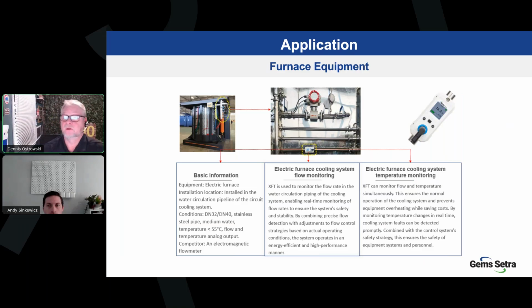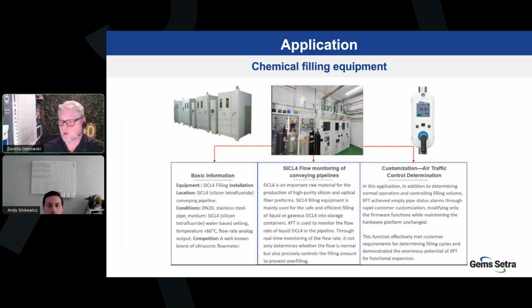Okay, and we have another application for chemicals. We had mentioned before, chemicals can be quite caustic. A lot of corrosion can happen in your equipment and in devices that are in line, right? So if you've got a clamp on, you eliminate those risks. You're not going to have any kind of contamination. You're not going to have any kind of corrosion. So it doesn't matter, as long as you know that sound velocity, right? As long as you know that of whatever chemical you're using, you can calibrate this device to measure that liquid flow.